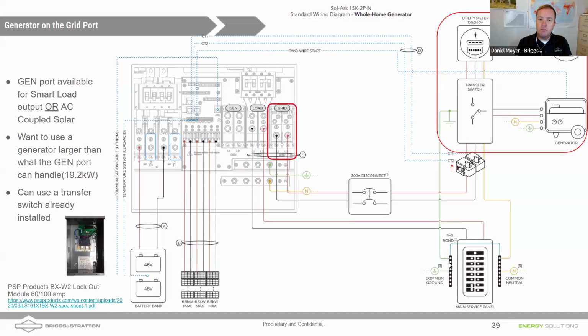Load grid coming in, loads coming out, DC coupled solar battery. So imagine the batteries are going low. What we're going to do is send a 2-wire signal to start the generator. The generator is going to start up. Normally this transfer switch would be running up and down, but it's going to tell this transfer switch to transfer. And now we're going to be bringing the generator in on the grid port, and we're going to take over the loads and charge up the batteries.